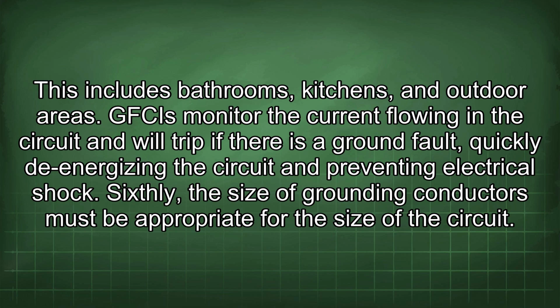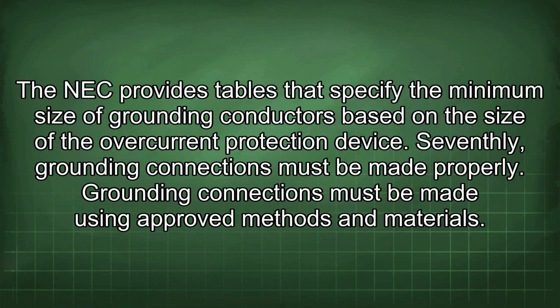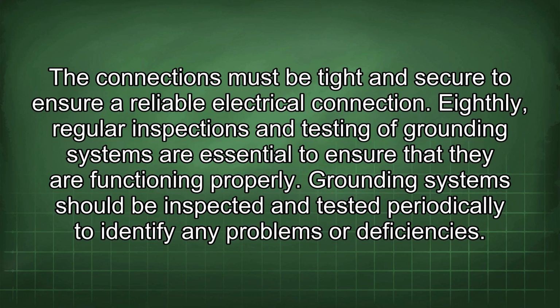Sixthly, the size of grounding conductors must be appropriate for the size of the circuit. The NEC provides tables that specify the minimum size of grounding conductors based on the size of the overcurrent protection device. Seventhly, grounding connections must be made properly. Grounding connections must be made using approved methods and materials. The connections must be tight and secure to ensure a reliable electrical connection.